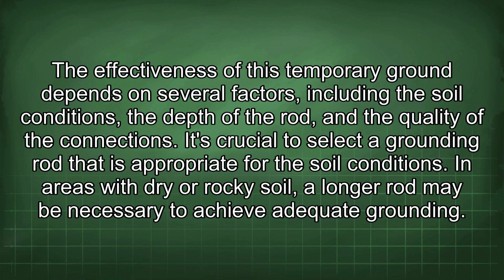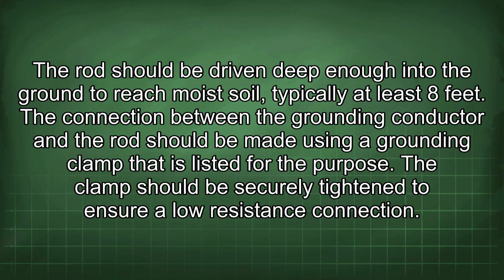It's crucial to select a grounding rod that is appropriate for the soil conditions. In areas with dry or rocky soil, a longer rod may be necessary to achieve adequate grounding. The rod should be driven deep enough into the ground to reach moist soil, typically at least 8 feet. The connection between the grounding conductor and the rod should be made using a grounding clamp that is listed for the purpose. The clamp should be securely tightened to ensure a low resistance connection.